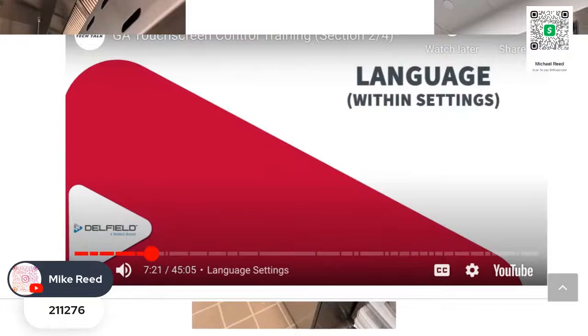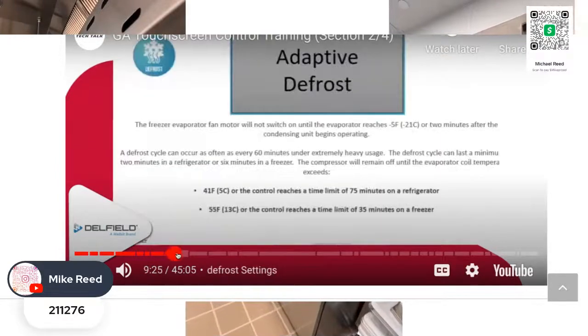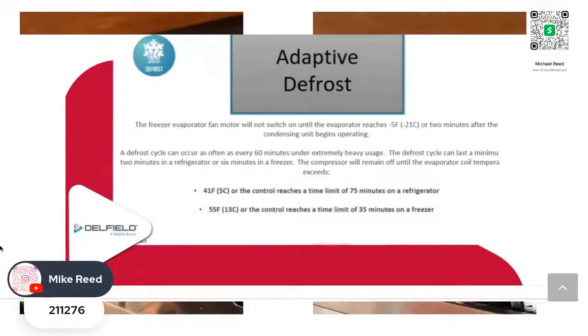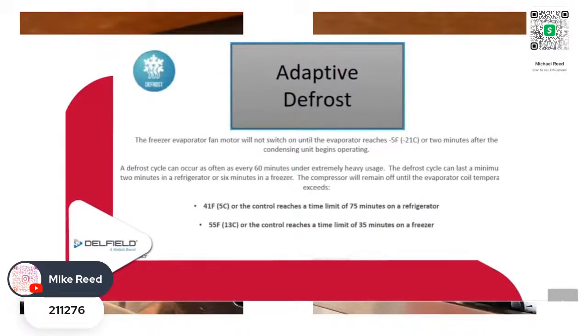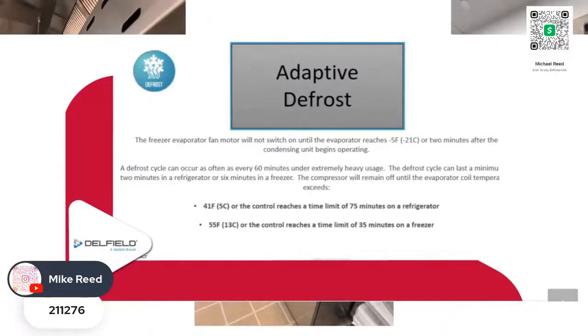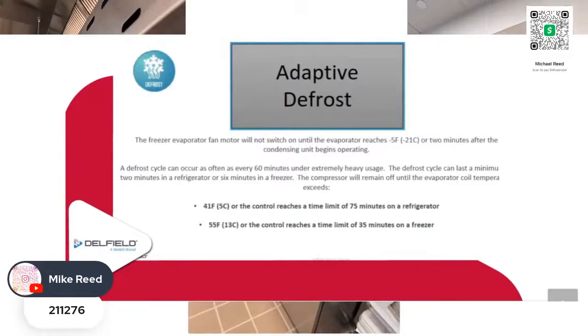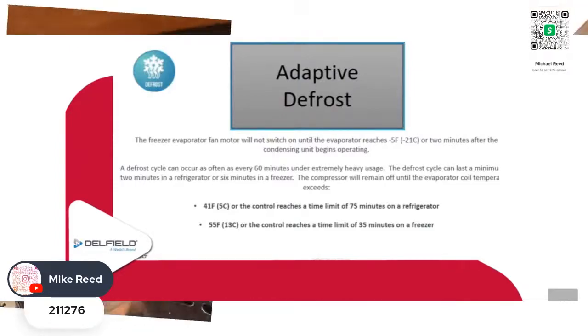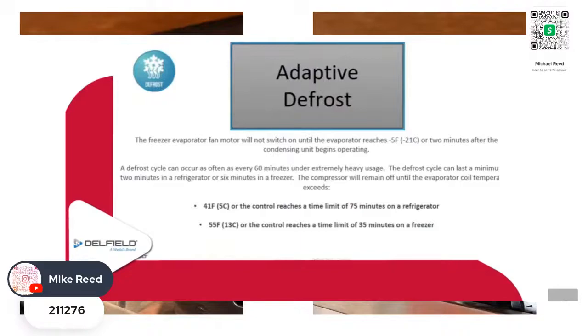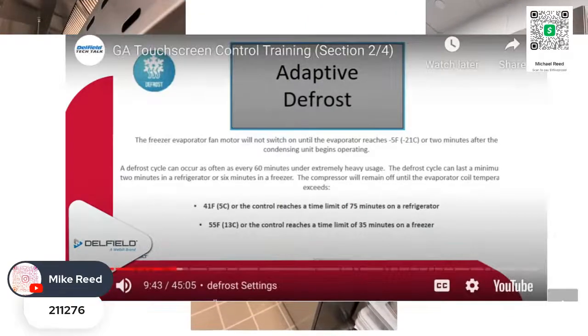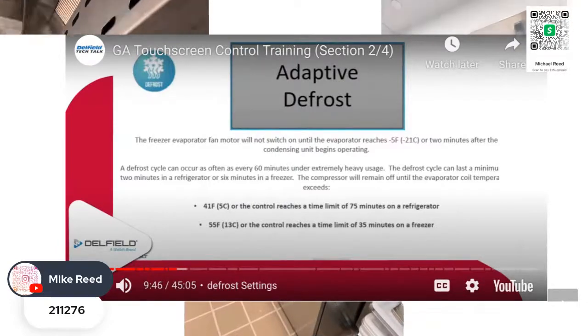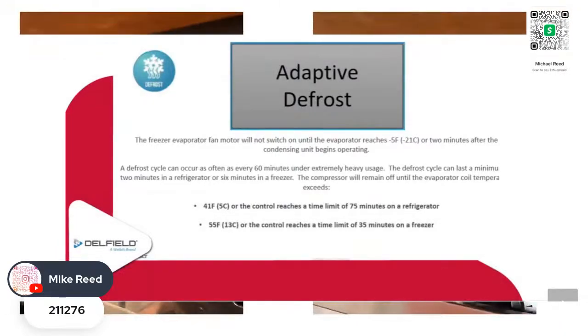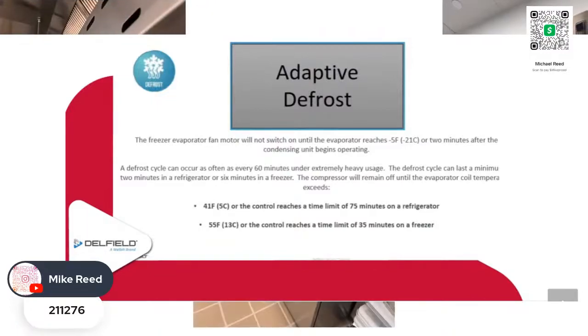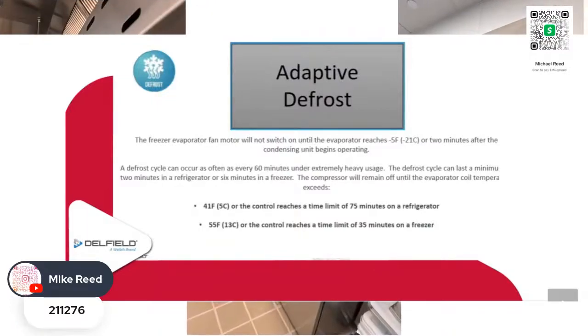He goes on and on like this, but this is the same thing, runtime and evaporator coil temperature. Again, the settings will vary a bit depending on if it's a cooler or a freezer. The freezer will go into defrost until it hits either a 55-degree coil temperature or 35 minutes of actual time. The refrigerator is looking at a 41-degree coil temperature or 75 minutes.